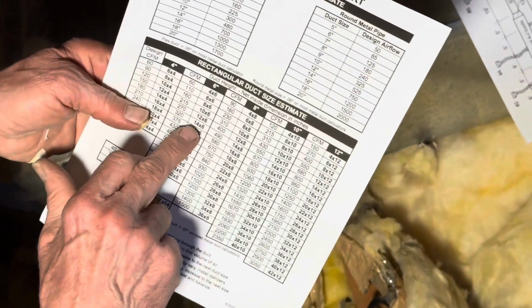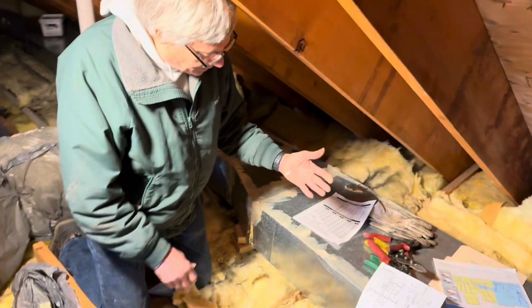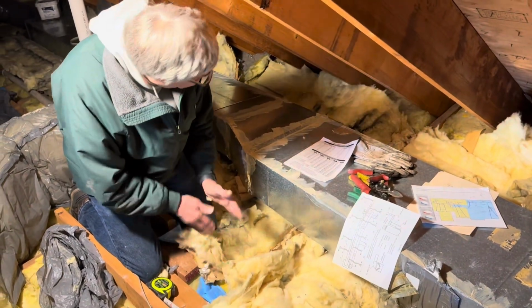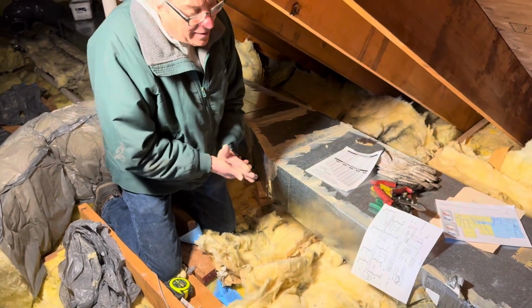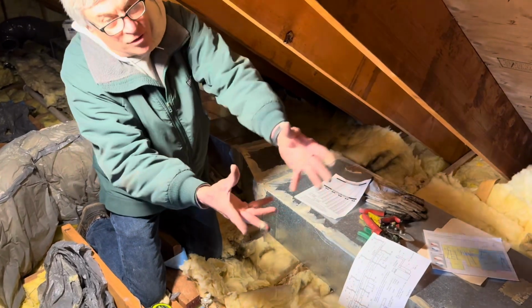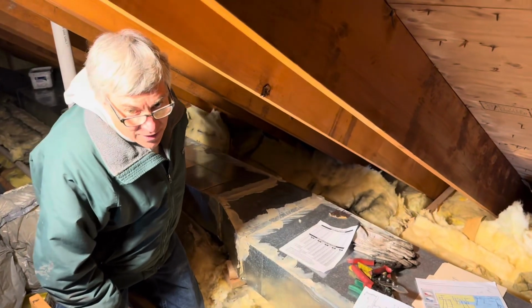And if we go to 6 and 14, that's 320 cubic feet a minute of air. So we're reducing that down because the available amount of air is now less. And it's less because we've already taken, with those 3 branch circuits, some of that air and given it to the rooms. So now we come over here and we still have to supply a bathroom and a closet.